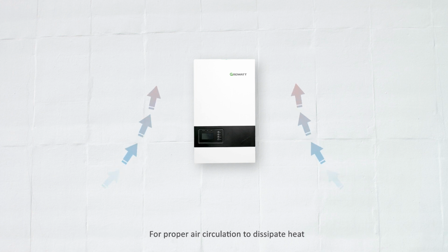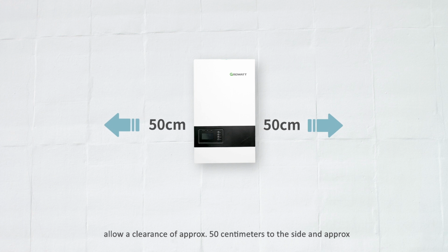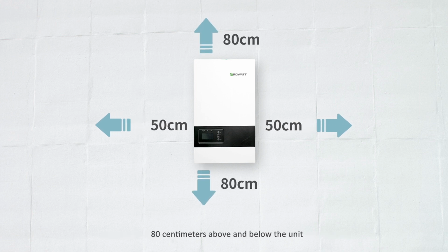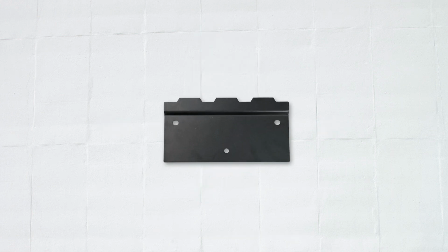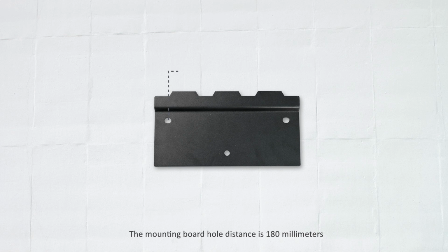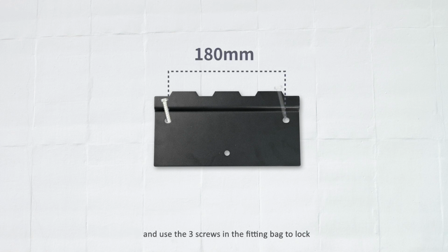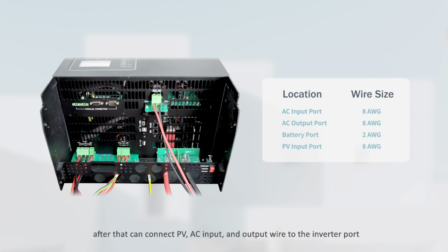For proper air circulation to dissipate heat, allow a clearance of approximately 50 centimeters to the side and approximately 80 centimeters above and below the unit. The mounting board hole distance is 180 millimeters, and use the 3 screws in the fitting bag to lock. After that, you can connect the PV, AC input, and output wires to the inverter ports.